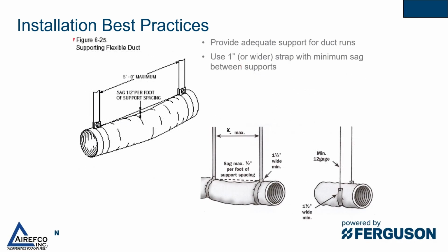Most of us have seen flex duct that's been run through an attic where the flex duct is just draped across the rafters, cutting off about half of the airflow that moves through the flex duct. When running flex duct, make sure that you properly support it per manufacturer specifications and that you hang it with at least a 12 gauge wire as specified, and that the strap that you are holding the flex up with is at least 1.5 inches wide to keep from deforming the circular contour of the flex duct so that the air will properly flow through the flex duct as you stretch it out through the attic.